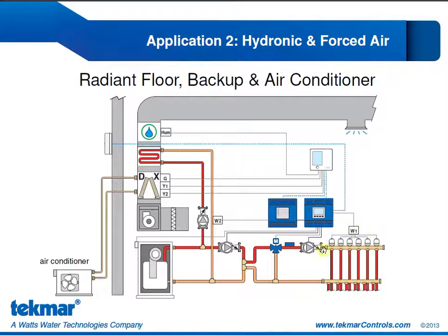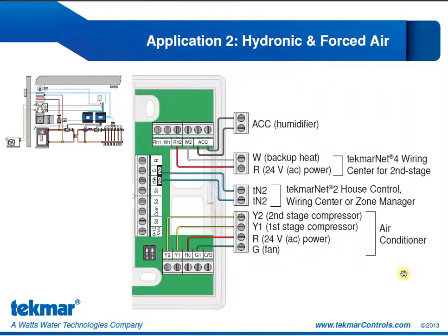Our second application with traditional heat-cool equipment is a radiant floor with a fan coil and an air conditioner. Our first stage of heat is the radiant floor. That's going to be controlled through the house control. Our second stage of heat is the fan coil. And if we're in cooling mode, we have up to 2 stages of cooling, controlled through the Y1 and the Y2 relays. Again, we see a humidifier in the ductwork to provide some humidity control.